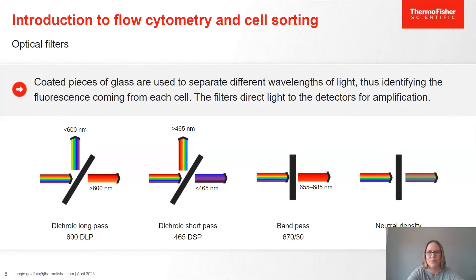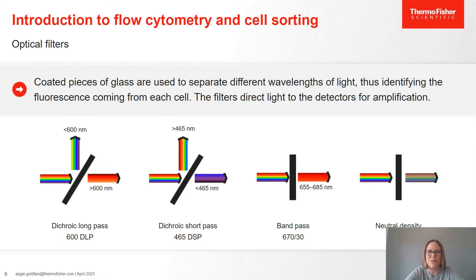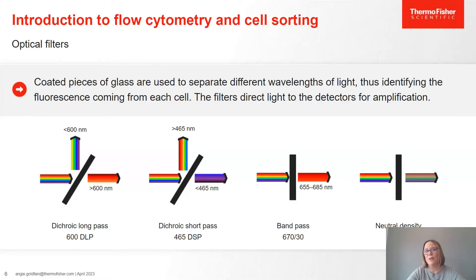To separate that light, we use optical filters — coated pieces of glass that separate the light into different wavelengths and steer it to the detectors. There are four main types of filters in flow cytometry: a dichroic long pass, which lets some light pass through and reflects others; a dichroic short pass, which lets shorter light pass through and reflects the others; a band pass, which lets a specific band of light come through; and a neutral density, which generally dims everything down — kind of like sunglasses for that signal. The same process of filtering and bouncing light is used for both scattered and fluorescent light, directing the light to detectors for amplification and processing.